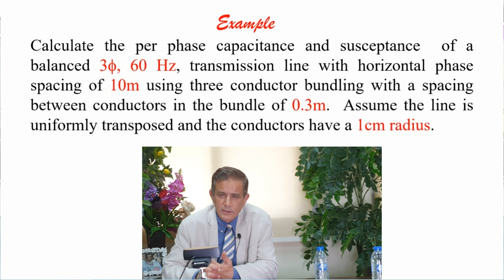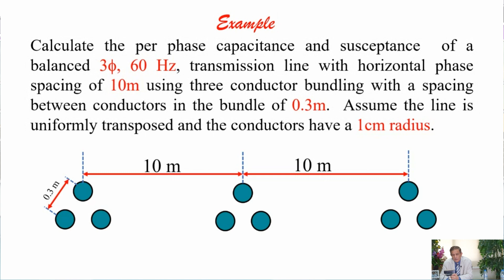We have phase A, B, C. The distances are 10 meters, and then I have 20 meters between A and C. If I multiply all of these together and take the third root, I will get the equivalent distance. For the bundle, the radius was 1 centimeter, converted to meters it's 0.01, and I multiply by the distances from the conductor to the others, 0.3 by 0.3, to the power of 1 over 3. This is simply the geometrical mean radius of the conductor. D, as we said, we multiply 10 by 10 by 20 to the power of 1 over 3.